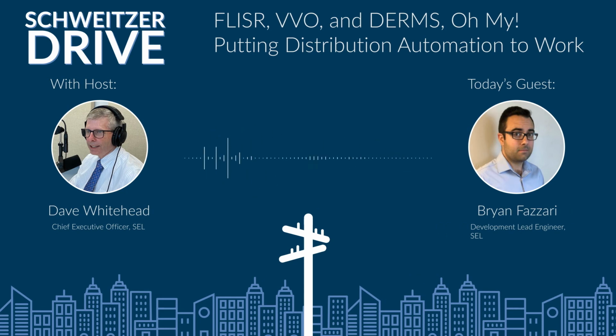But almost immediately we realized, hold on a second, faults can happen on these conductors. I don't want to deal with that up at the dam. I want to deal with that as close to the fault as I can, so that I only turn off a little piece of the power grid instead of the whole thing. So we have this concept of reclosers. They're pole top devices and they can trip the line close to where the fault is.